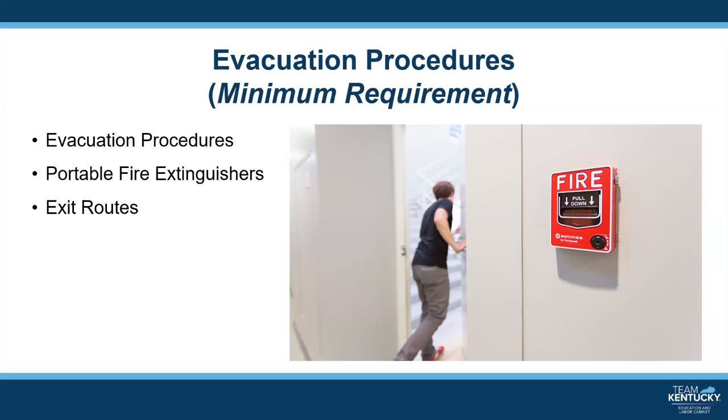Evacuation procedures also often describe actions employees should take before and while evacuating, such as shutting windows, turning off equipment, and closing doors behind them. Sometimes a critical decision may need to be made when planning: whether or not employees should fight a small fire with a portable fire extinguisher or simply evacuate. Portable fire extinguishers may be integrated into the emergency action plan. However, keep in mind that if you're going to require employees to fight a fire, even in the incipient stage, the employees will then be required to have training on fire extinguishers. This means more than just explaining the method and includes hands-on training with fire extinguishers.